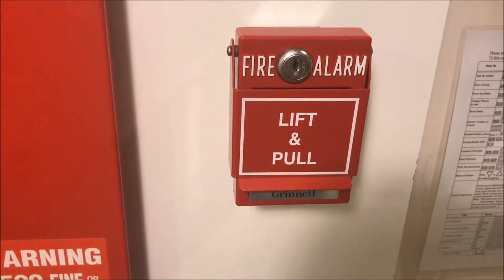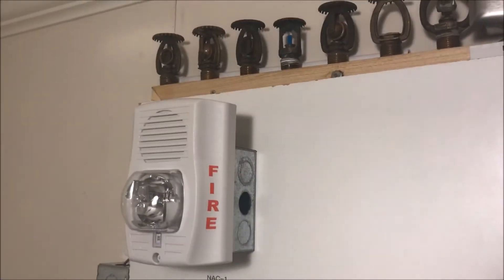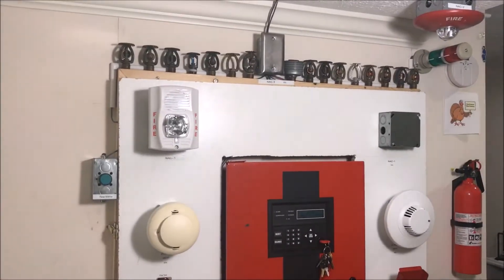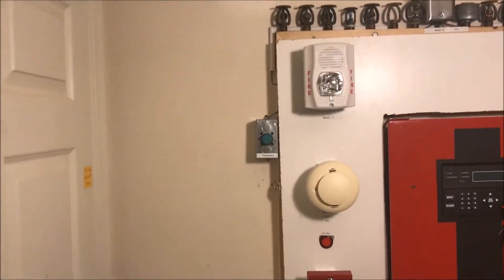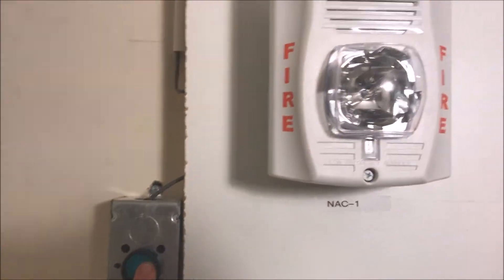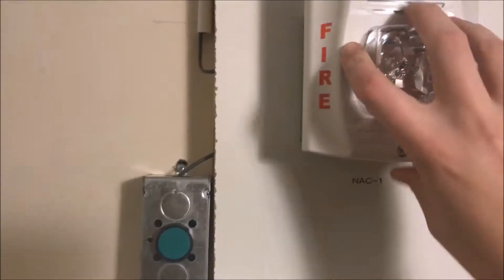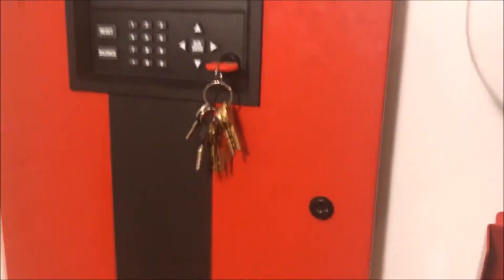I've already spent three minutes on the intro, so let's start pulling some stuff. We're going to come over to the Grinnell station and pull it. Because this is sadly a two-wire device, there is no audible silence, but the strobe up here is still flashing. These are in sync — I don't know how well you can tell, but they are in sync. I'm just going to reset the pull station.